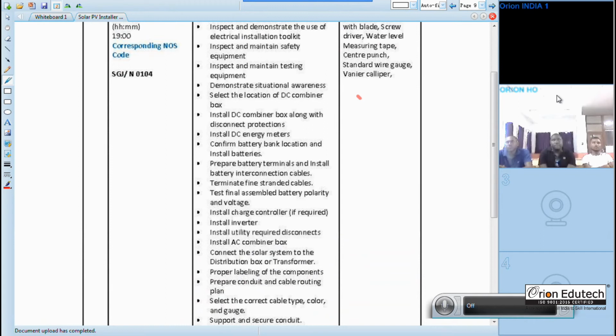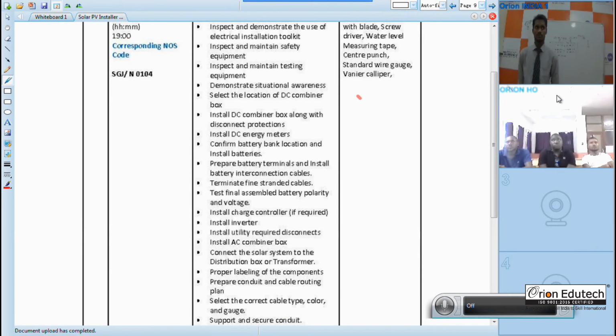Confirm the battery bank location and install the battery. Prepare battery terminals and install battery interconnection cables, terminate fine stranded cables, test final assembled battery polarity and voltage, and install the charge controller if required.